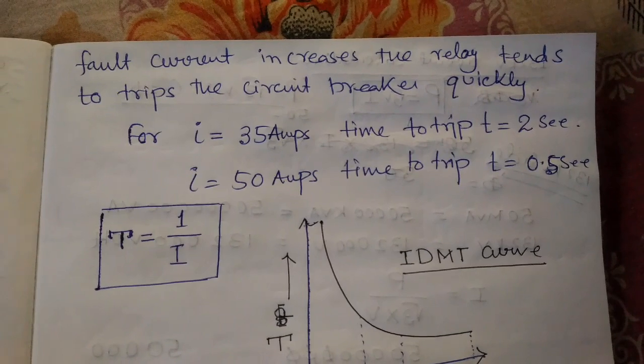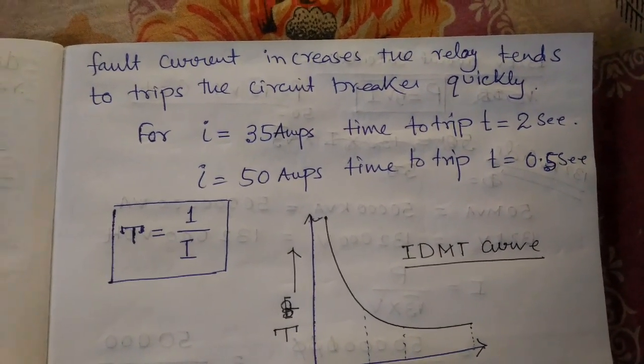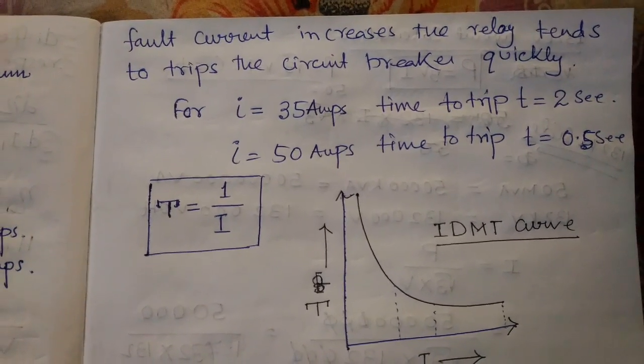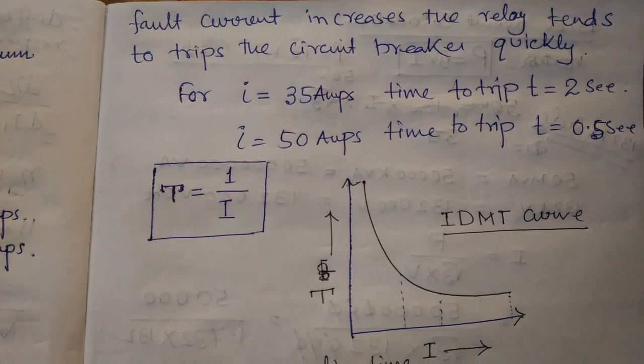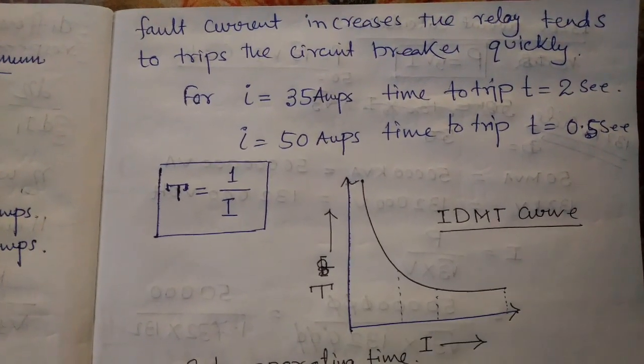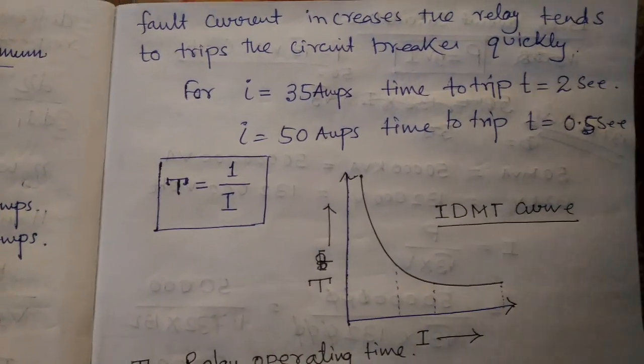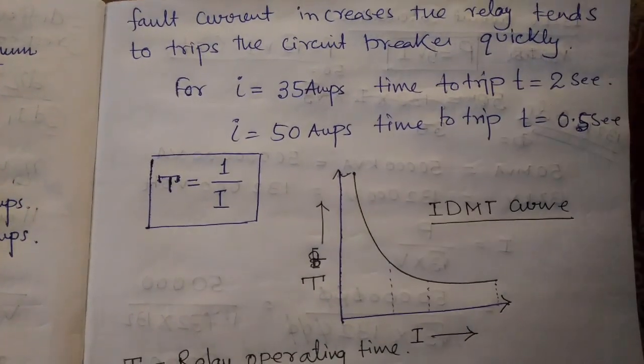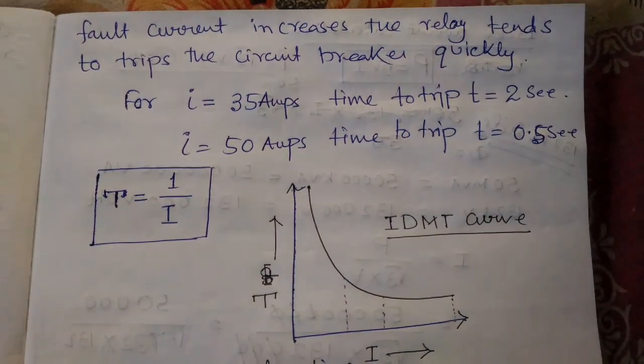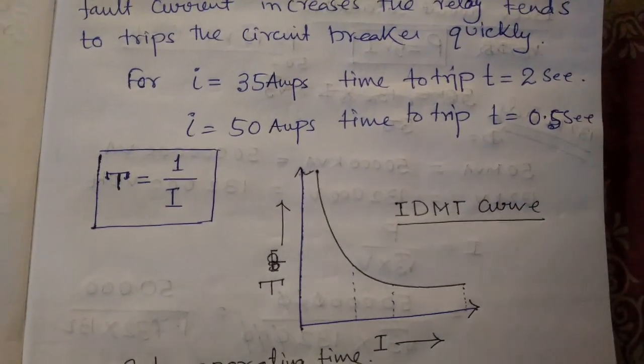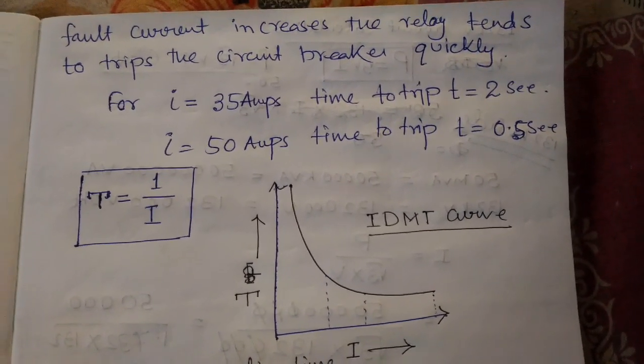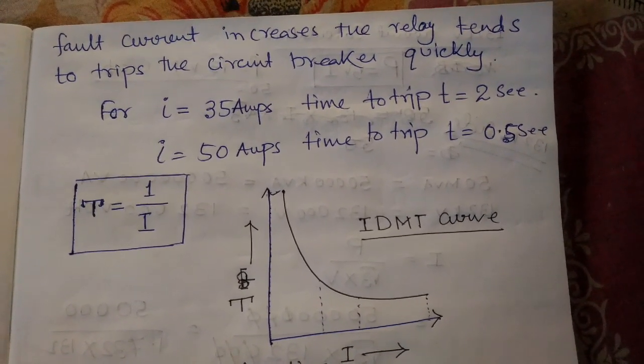Now we will discuss an example of current with respect to time. For example, if the current flowing through the breaker or relay is I equal to 35 ampere, the time to trip the IDMT relay is 2 seconds. If the current continues increasing and reaches 50 ampere, the time of tripping is 0.5 seconds.